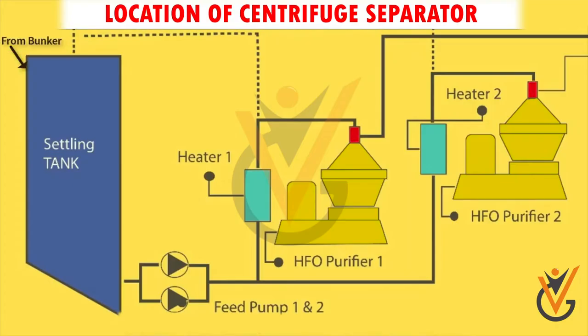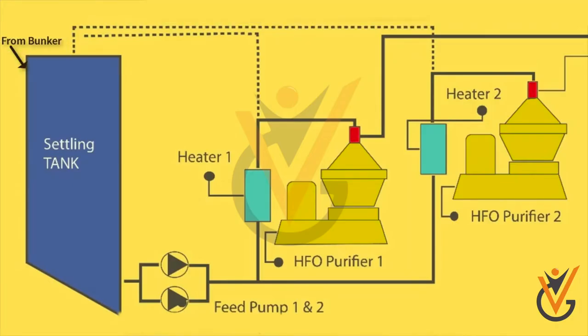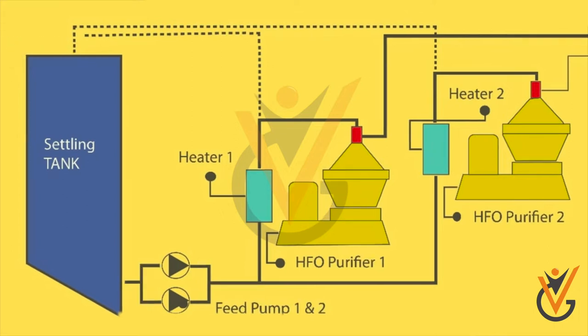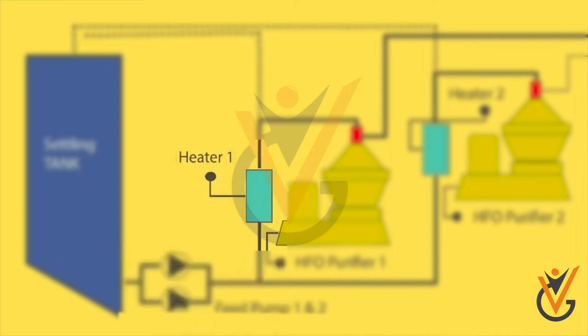Location of centrifuge separator. After receiving the fuel oil in bunker tank, we transfer them to first storage tanks and then to settling tanks, where it is stored and heated up to 50 to 60 degrees Celsius. There the heavier contaminants and water gets separated under the effect of heat. Fuel from the settling tank is drawn out through feed pump and passed through heater to raise its temperature to around 80 to 90 degrees Celsius.